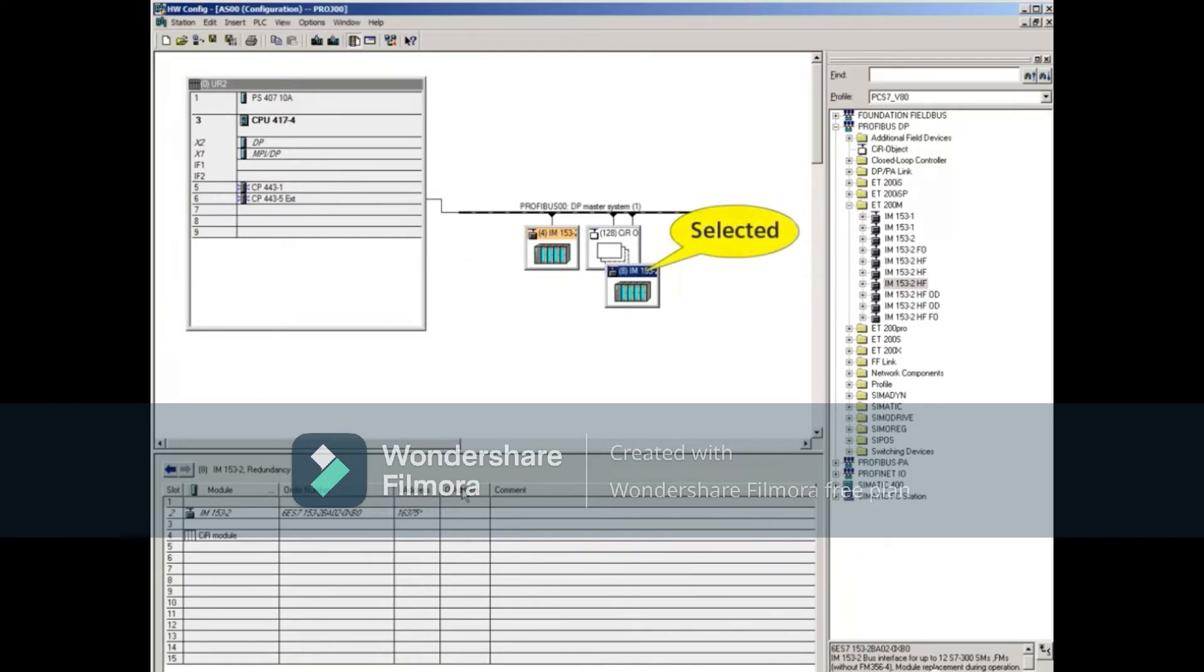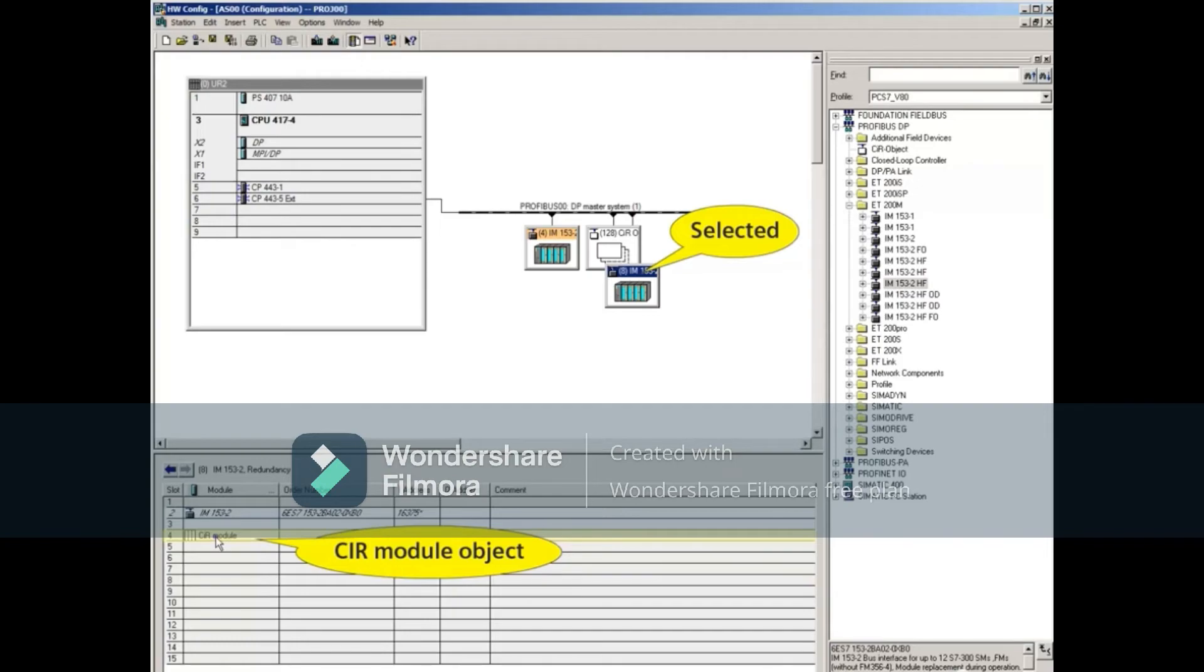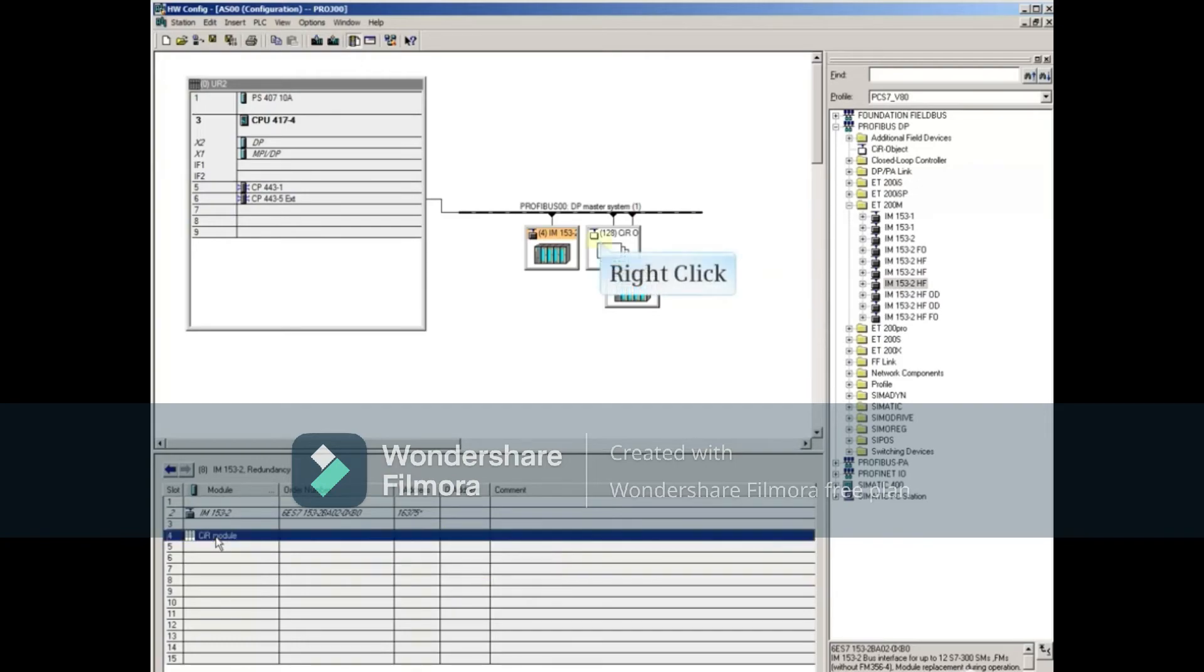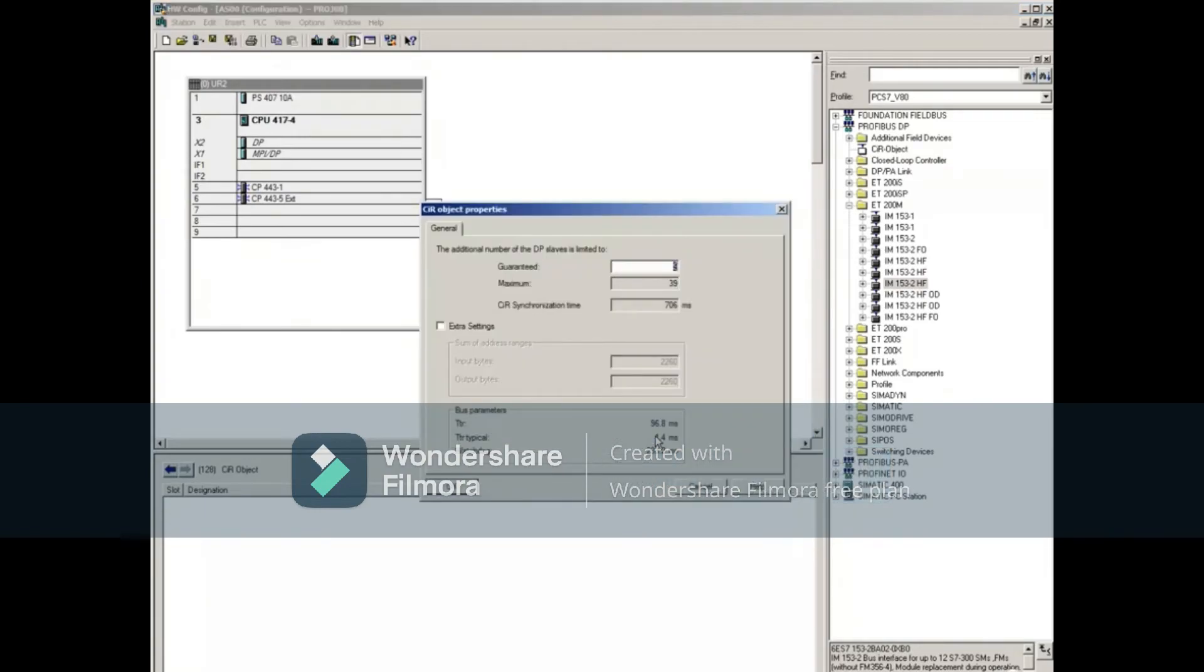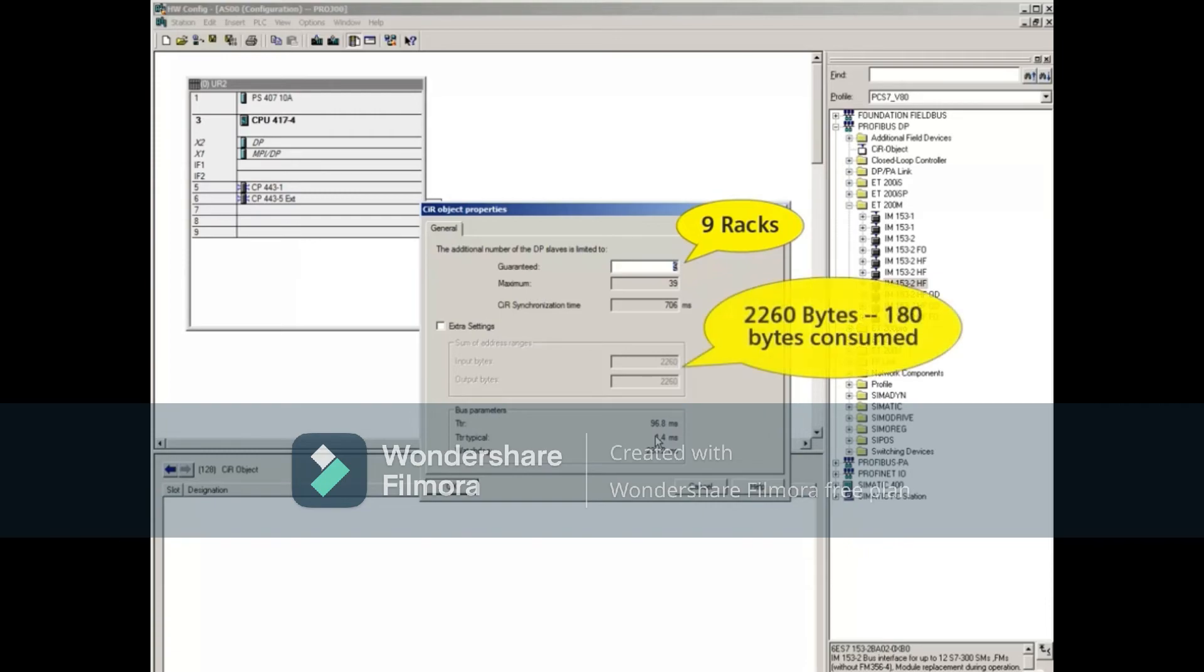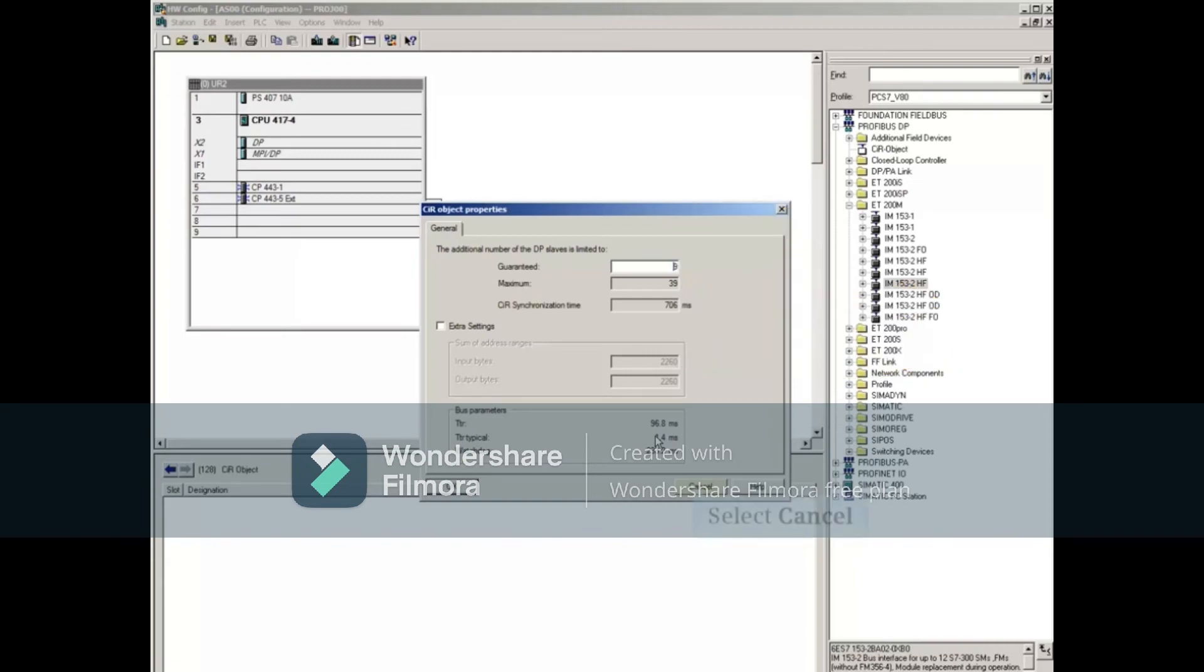Notice the CIR module object in the ET200M rack. Right-click the CIR object, and open its properties. Notice that the guaranteed racks have reduced to 9, and 180 bytes of memory have been consumed. Close the CIR properties.